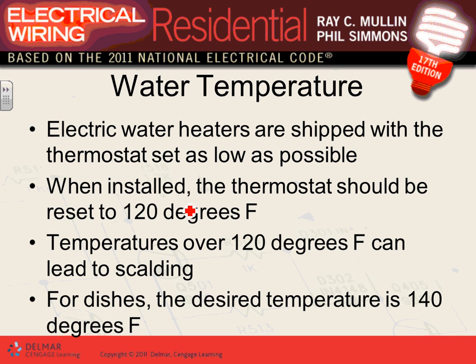This is just a couple of things, guys, about the temperature, and temperature over 120 can cause scalding. So there's a couple of settings for the temperature. For a dishwasher, the desired temperature is 140. You can see for a dishwasher, the temperature is hotter than the safe temperature for scalding. That's for killing germs and so forth. When installed, the thermostat should be set at 120 degrees Fahrenheit so you don't get scalding. This is related to the water temperature of the water heater though. Then the dishwasher will take this water and boost it up to 140 just inside the dishwasher. Not when you take your shower at 140. Okay, so that's just a couple of things about temperature.